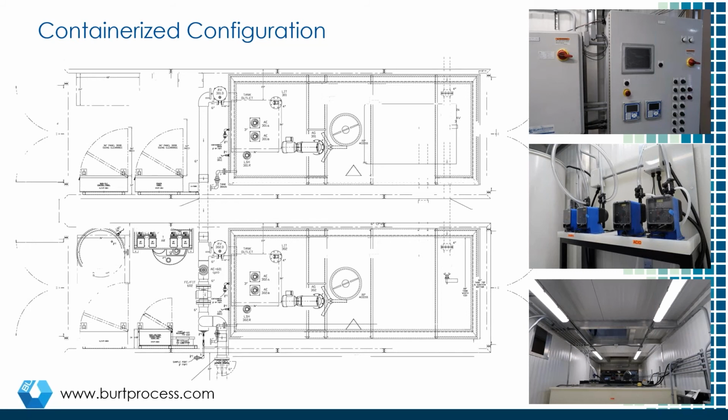And it's also another reason why sometimes people actually put a separate power feed also just for the utility. So you can kill the system, but leave the lights on, leave the HVAC system going, and then allow you to service the system properly or perform any maintenance or shutdown on the system while doing that.